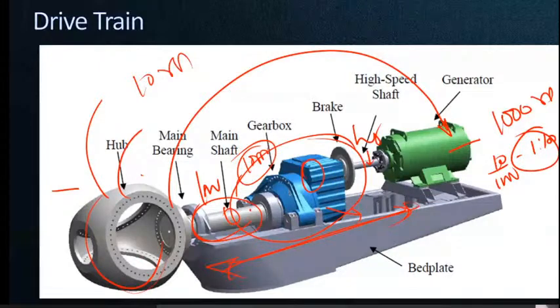Whether I can use a parallel shaft gearbox depends on the capacity. Mechanical engineers know there's parallel shaft gearbox or planetary type gearbox. For parallel type, I can't use it for high capacity because there will be a bulge. In case of a low capacity turbine, for example less than 500 kilowatt, I can use a parallel shaft. In case of a megawatt class turbine, I cannot use a low speed parallel shaft gearbox.